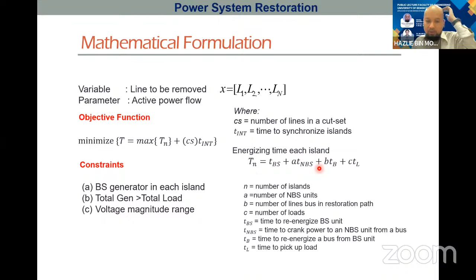This is the detail of the energizing time for each island. Example of the system - this is a 39 bus system. First we want to identify the islands, then create the islands, so you have island 1, 2, and 3. We restore the islands at the same time in parallel, step by step. After that, we connect here - the red one here is the connection. After every island 1, 2, 3 has been energized and is already operating, we connect each of these islands.